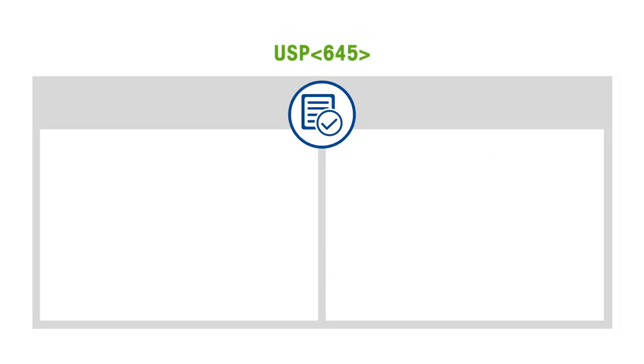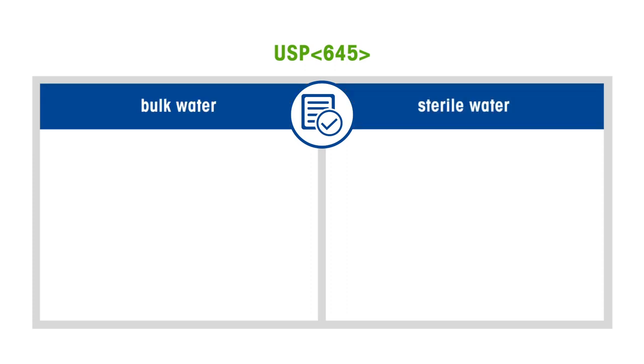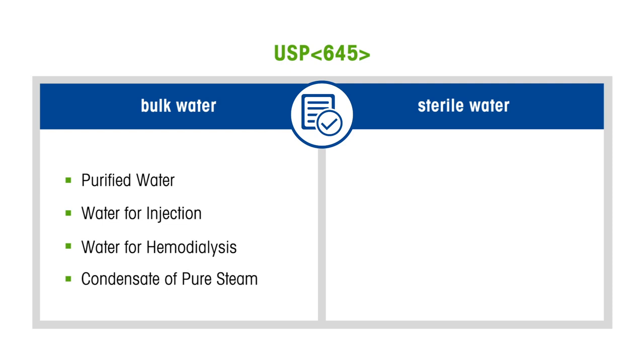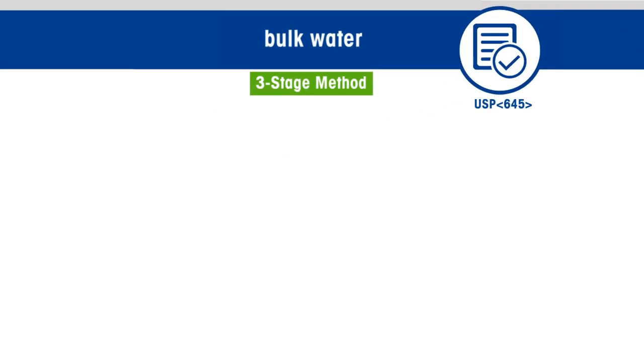The United States Pharmacopoeia 645 chapter defines the suitability of bulk water and sterile water samples through conductivity readings. The procedure mentioned under the section bulk water applies to purified water, water for injection, water for hemodialysis, and condensate of pure steam. It is a three-stage method.